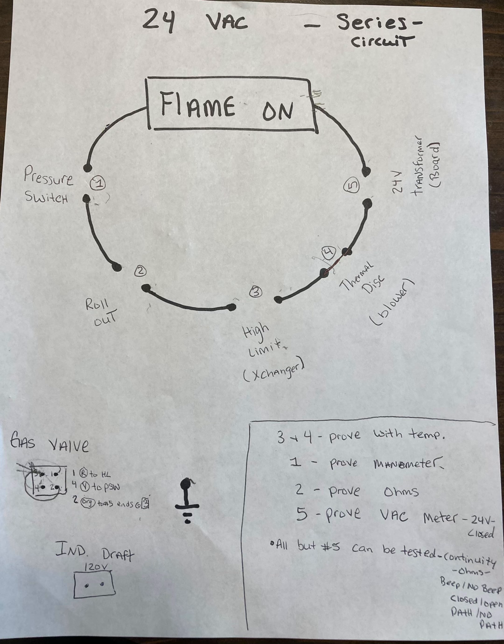But say that you're proving it. You're seeing that the pressures are being met, but that switch still isn't closing like it's supposed to. It's a bad pressure switch. We didn't guess. We didn't parts change. We proved it with our tool. So number one absolutely can be tested with a manometer to prove its authenticity.